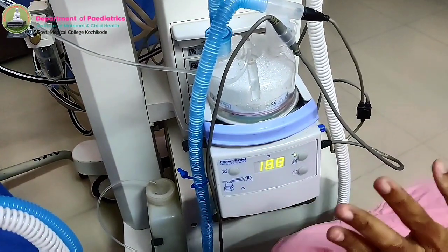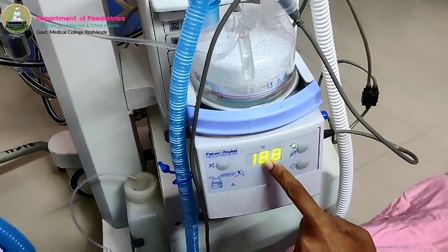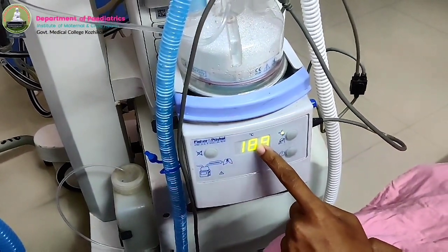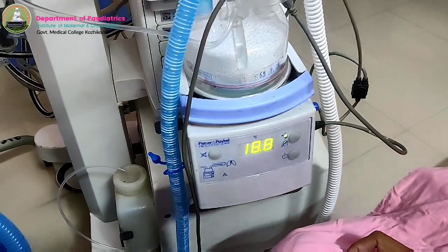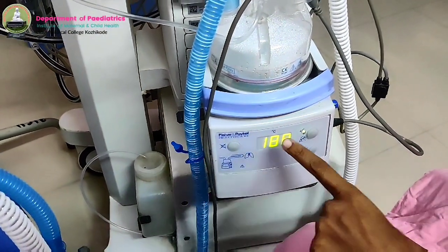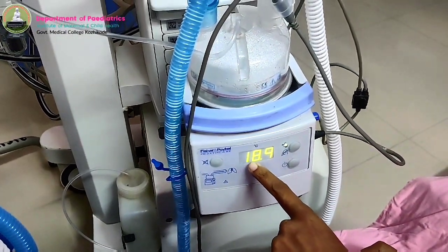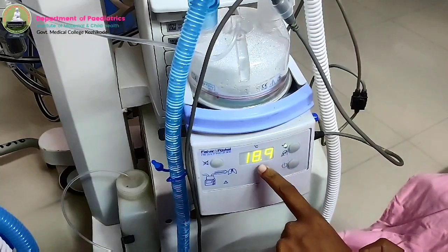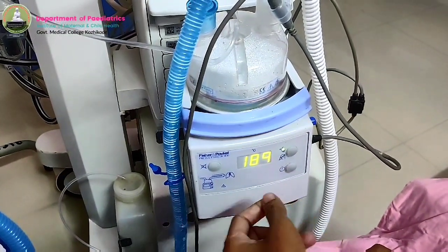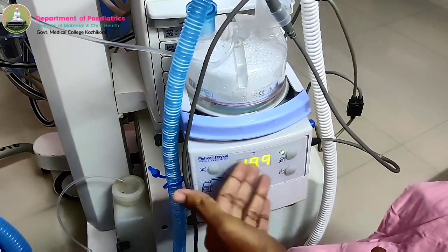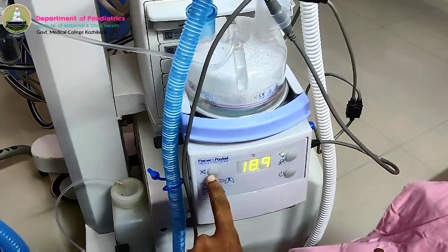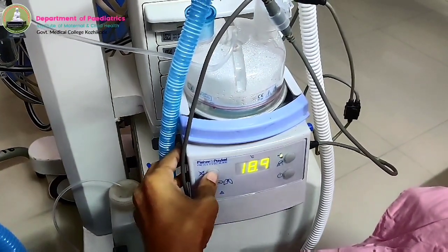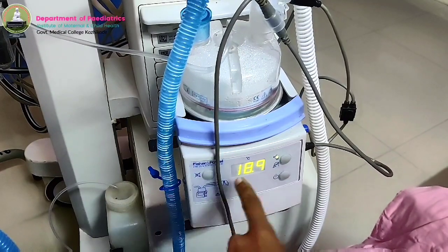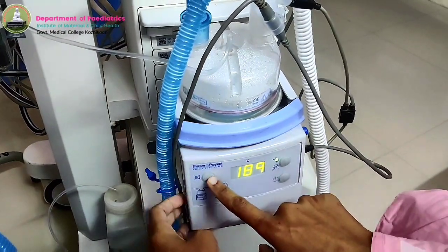So by default, the temperature shown here indicates the temperature of air near the patient end. Now see, the temperature is 18.9. That is not acceptable. We want 37 degree. So with this temperature, usually the alarm will ring and you can just silence the alarm by pressing this button. So this is for silencing the alarm.